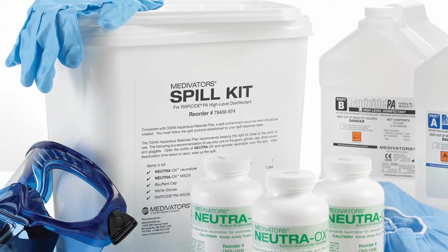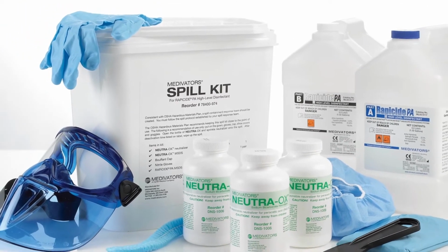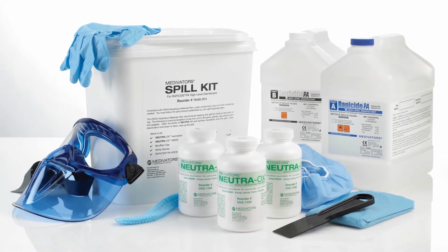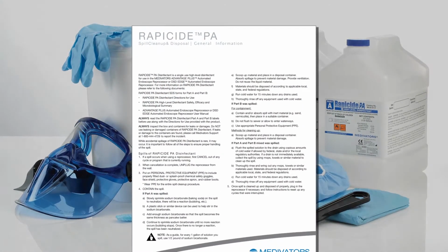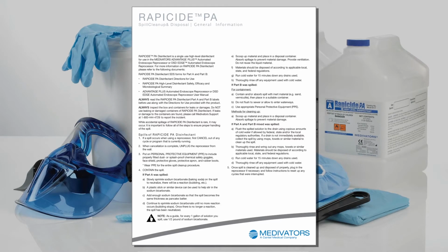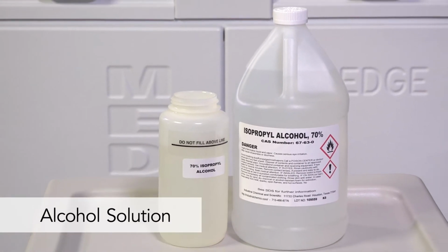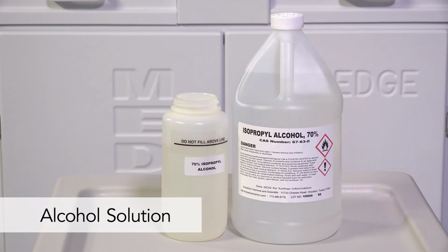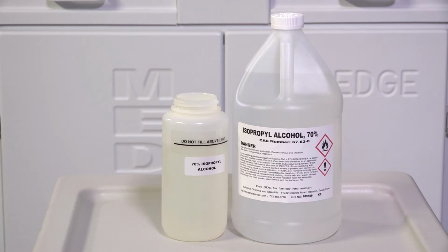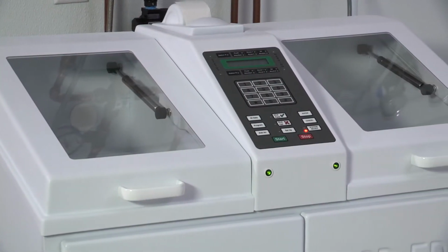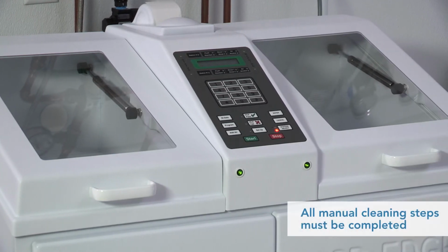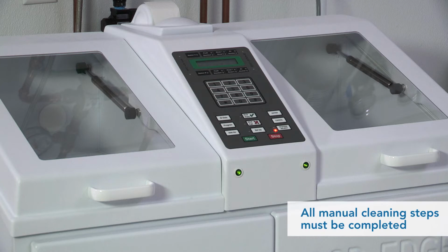During the in-service, you will receive training on spill containment, neutralization of Part A, and safe disposal of Part A and B. The Rapicide PA Disinfectant Spill Cleanup and Disposal form is in the in-service packet, shipped with your AER, or found on our website at www.medivators.com. The DSD EDGE Reprocessor utilizes 70% isopropyl alcohol per most endoscope manufacturers' manuals and society guidelines. The DSD EDGE Reprocessor has an optional detergent cycle. Enabling the detergent cycle does not replace completing all manual cleaning steps.